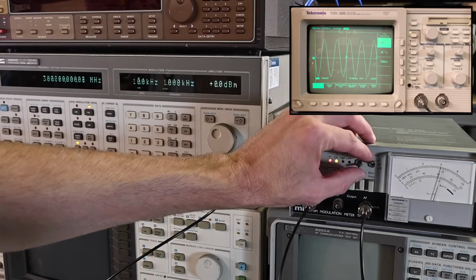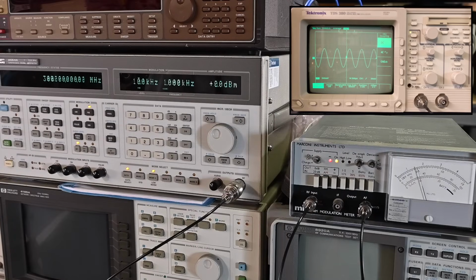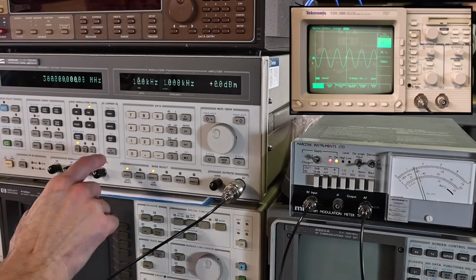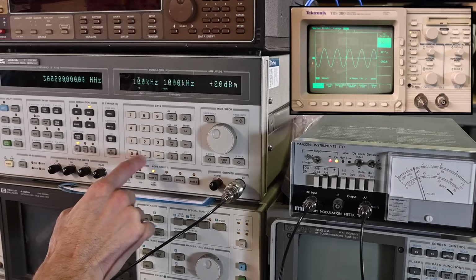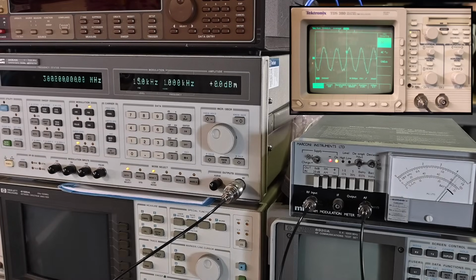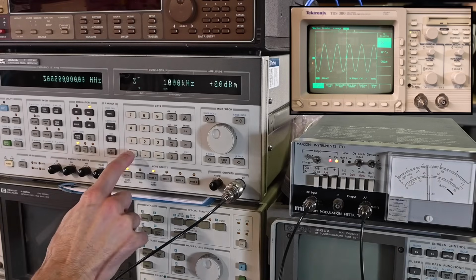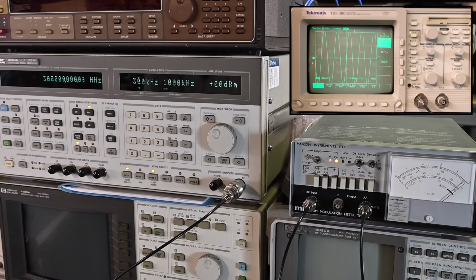If I take this and go to times 2, so now 15 times 2 is 30. Half of that, if I go to 15 kilohertz, should be about halfway, and yes, very close to halfway. 30 kilohertz should be full scale — yes it is, I just wasn't looking at the oscilloscope there, it's too large of a signal. So no problems with that.